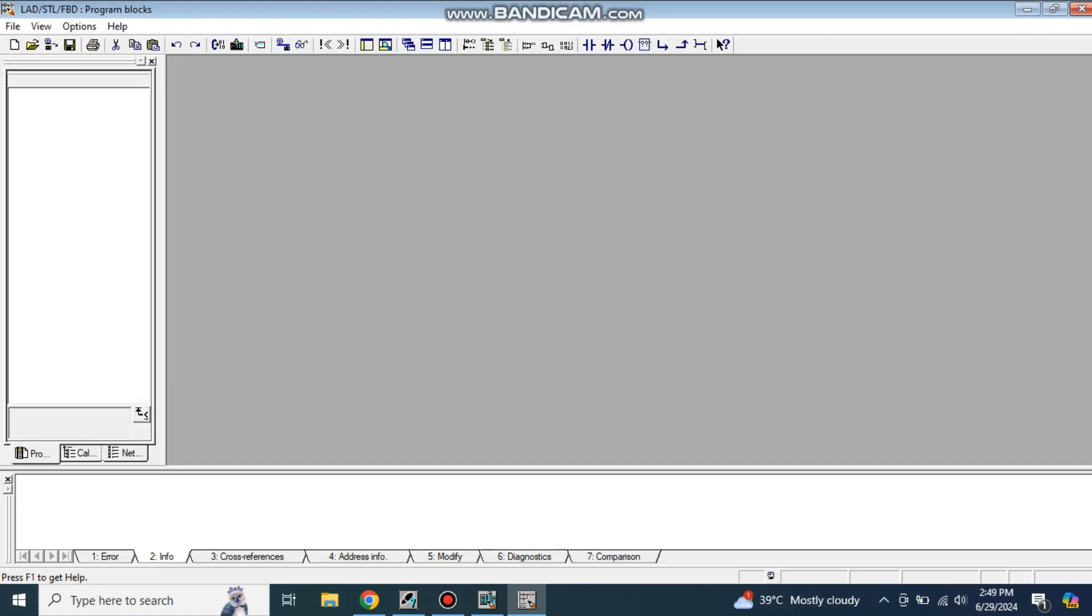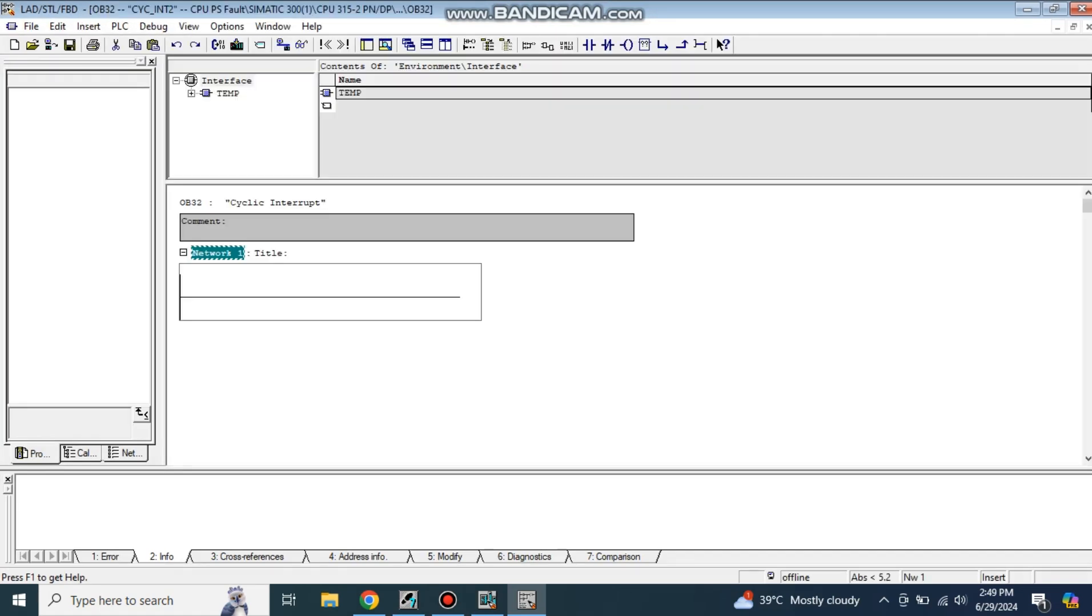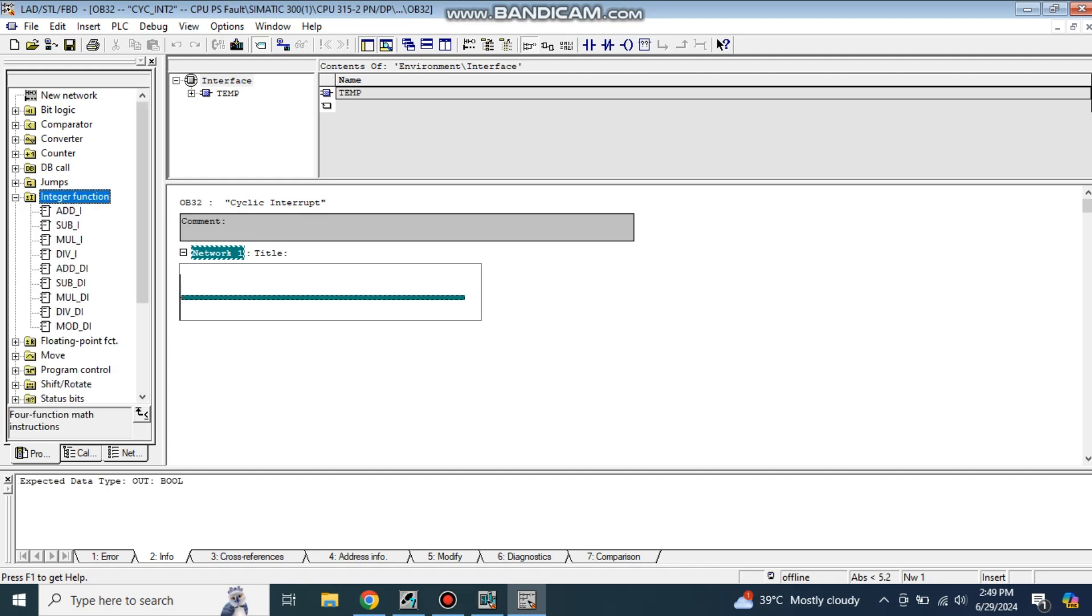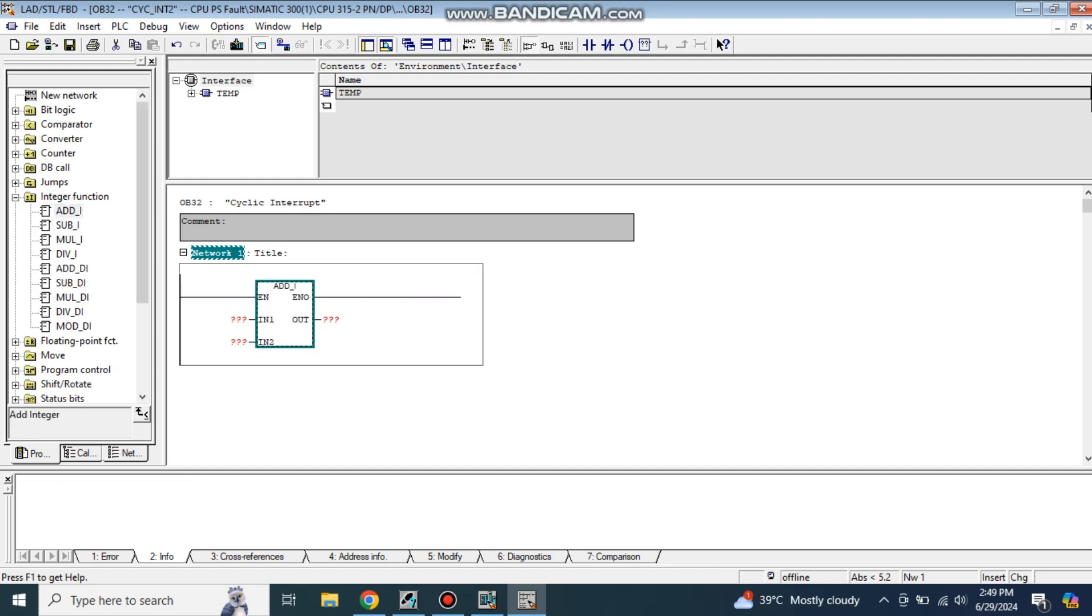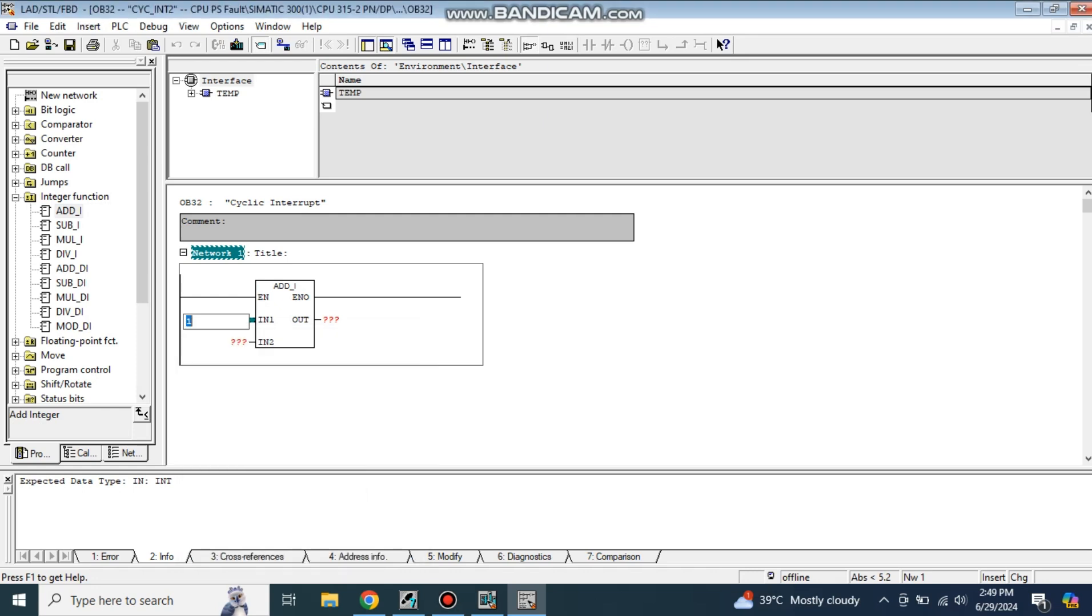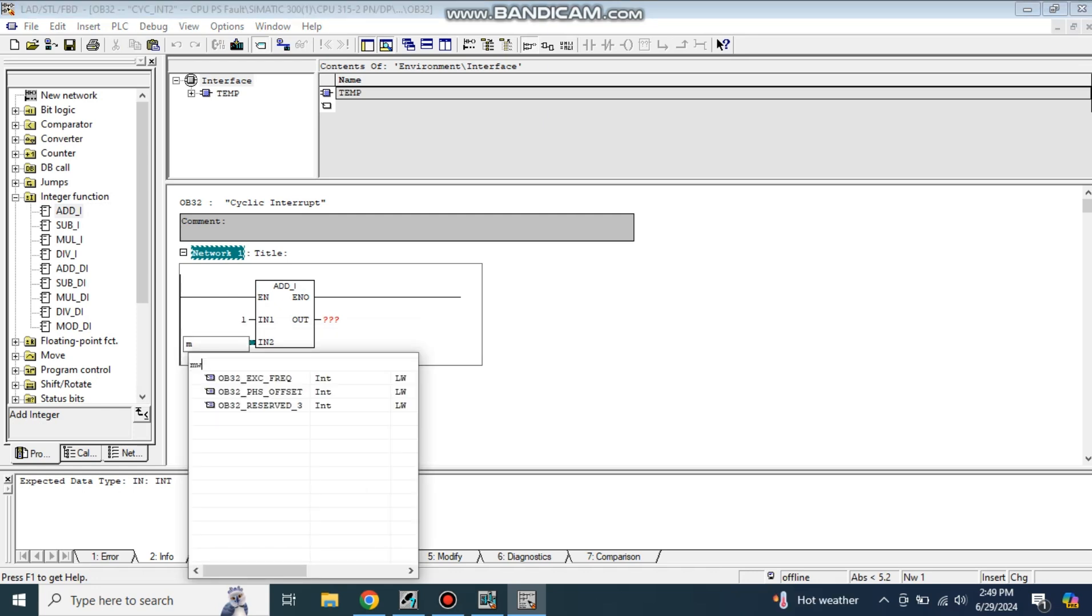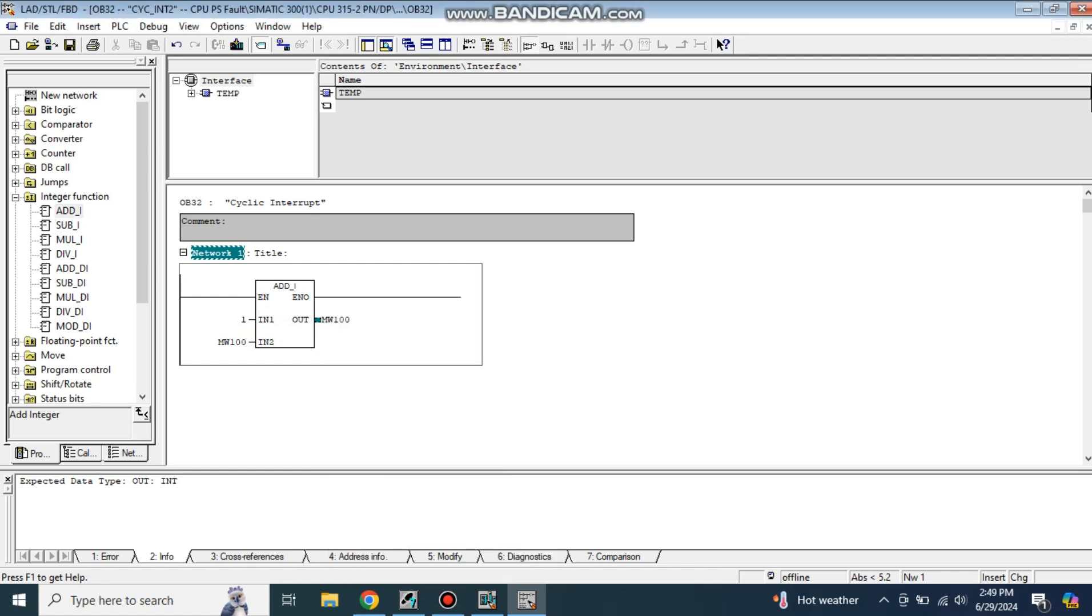What I am going to do is make a simple code in this cyclic interrupt OB32. It will count one after one second, keep counting one after one second. Basically, you will see a counter keep counting from zero, one, two, three, four, five and so on. I will take here an integer function, add integer, and tell it to add in the memory. Let's say memory word 100 and save also in memory word 100. Just save it.